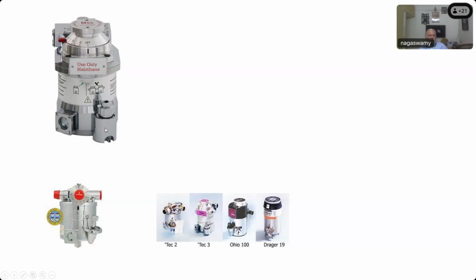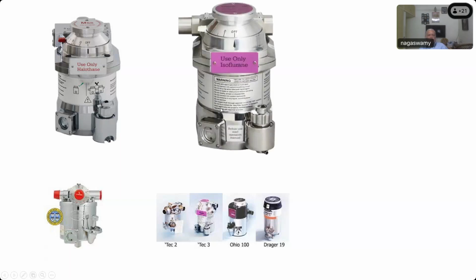To empty the vaporizer, you can use this same cap, inverting it and then opening the stem like thing. Then all the liquid inside the vaporizing chamber will pour out through that. You can collect it in the same bottle and then close that stem with this and then replace the cap. Okay, so that is the mechanism by which it is done. You can see it more clearly here.